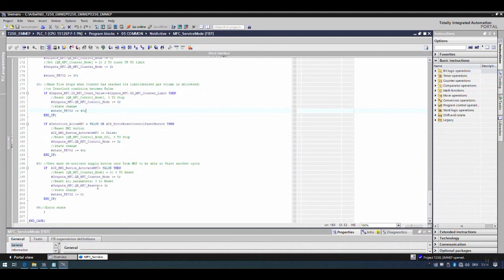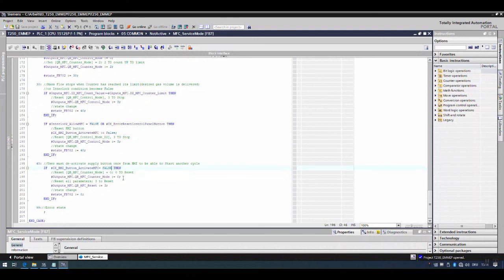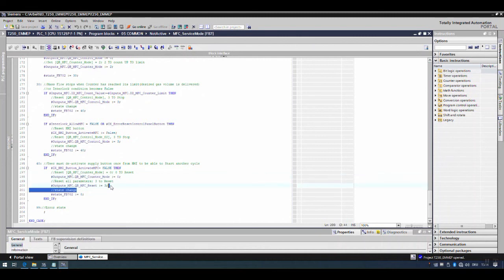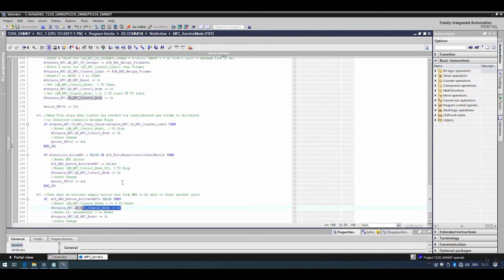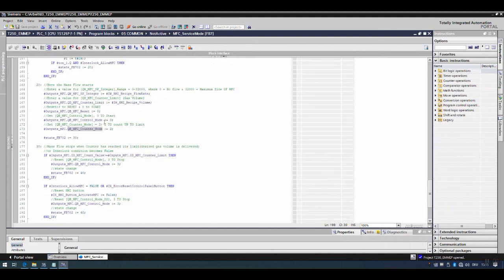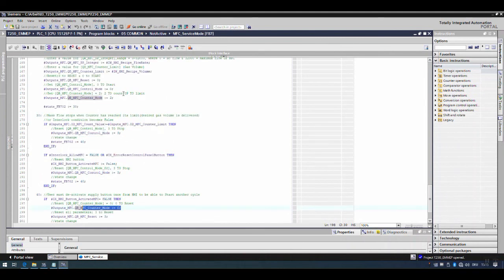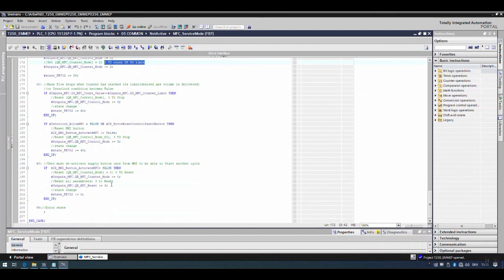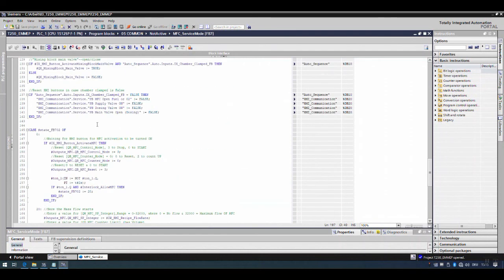In state 40, if the HMI button is pressed to close the MFC, the displayed volume value is reset to zero and the counter mode is reset. There is also an MFC reset parameter. Counter mode 0 means reset and 2 means count up. Resetting deactivates the MFC. This is just a basic explanation and a basic program to test whether the MFC is working.